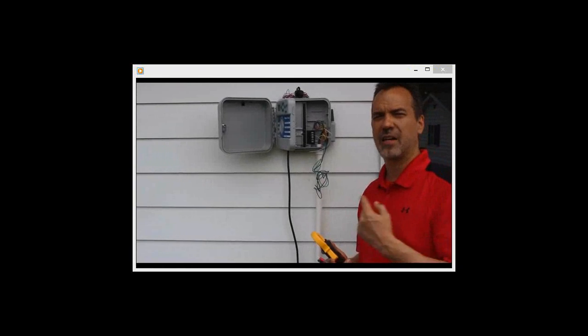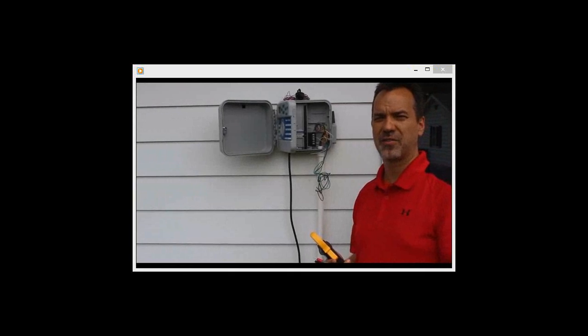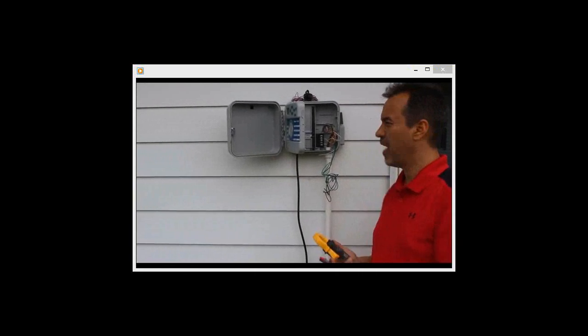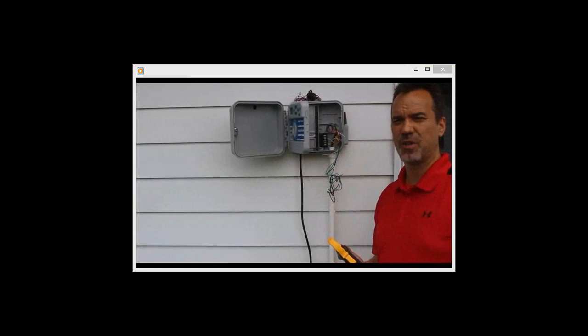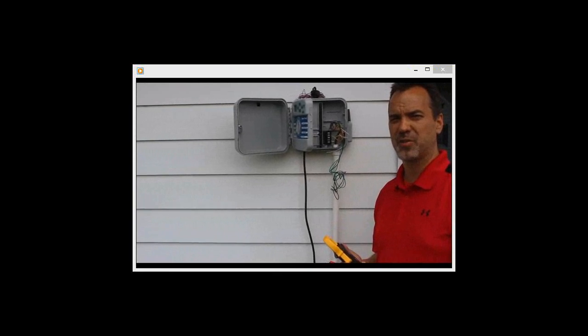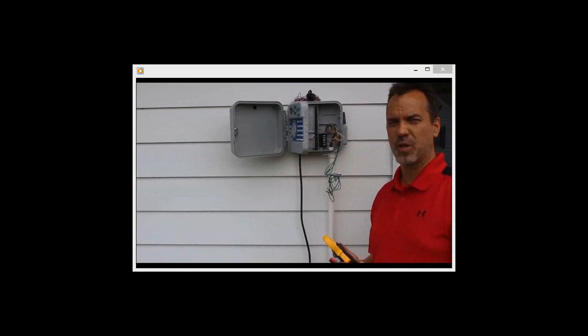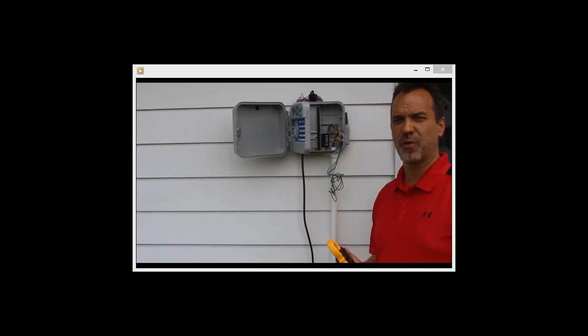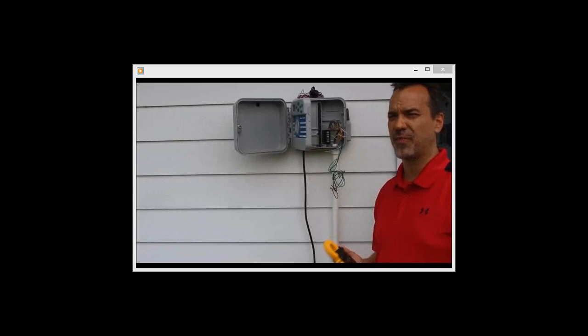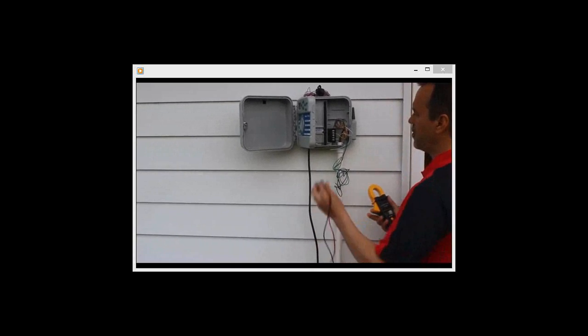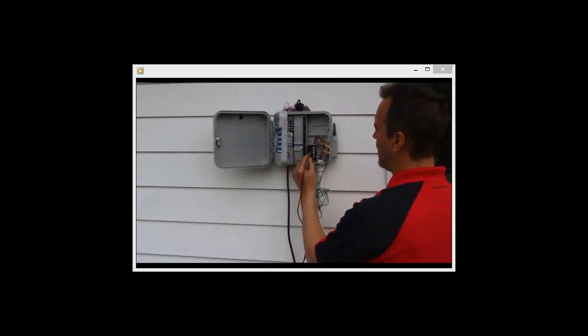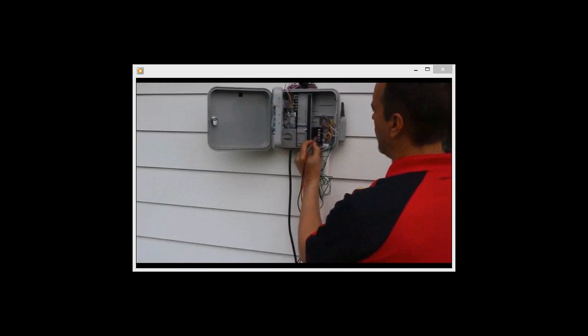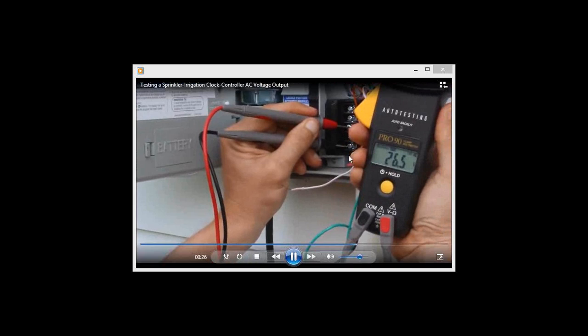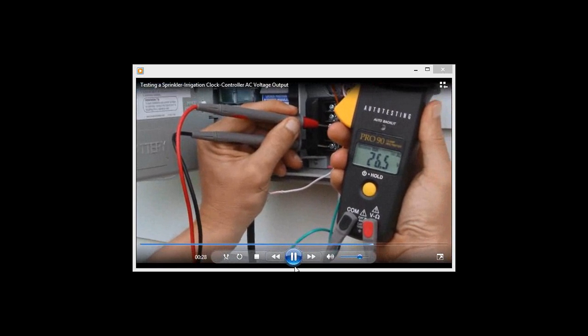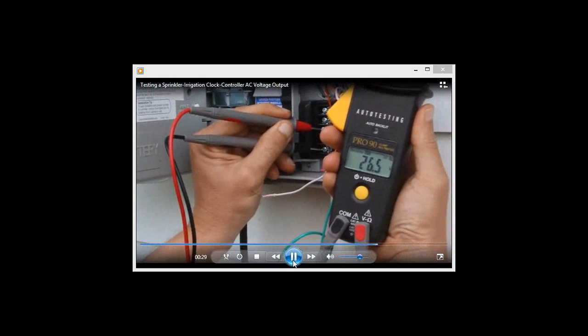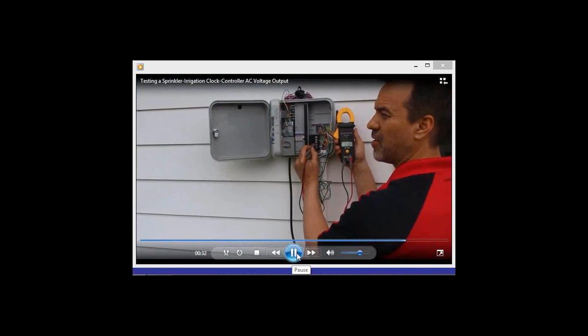Now I want to check the clock output to make sure that that's good. So on zone 1, we've activated zone 1 using the clock, using the manual controls. And if the clock is working properly, we should see 24 volts at that station. So I'm going to put my leads first on the common wire and second on station 1. And I should get 24 volts or somewhere similar to it. Here I'm getting 26 plus. So that output is correct at that zone.